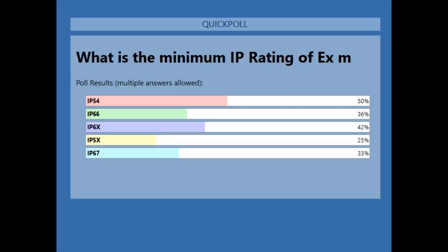Okay, so the correct answer is, for cable gland entry into any device, 60079-0, Annex A3 or A, minimum IP ratings for EPL Ma or EPL Mb, Ga, Gb, is IP54. But you have to use a sealing means, an IP washer, during testing to prove IP54.